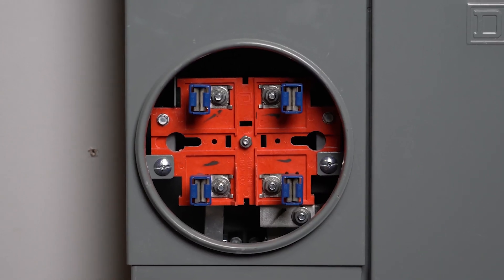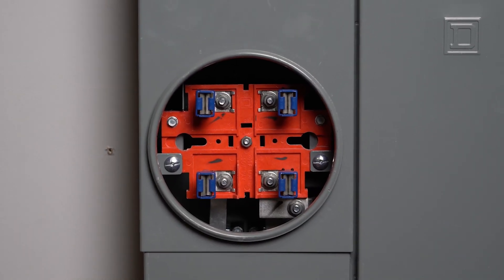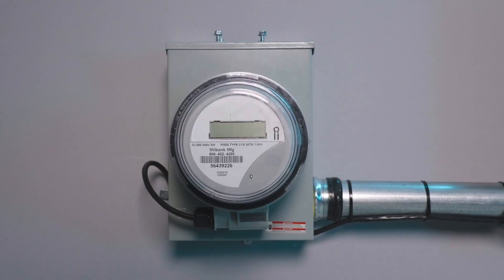If either the meter or meter socket displays damage or is otherwise not in good condition, stop the installation and work with the customer to have the meter socket replaced or install Backup Switch in a standalone meter panel.